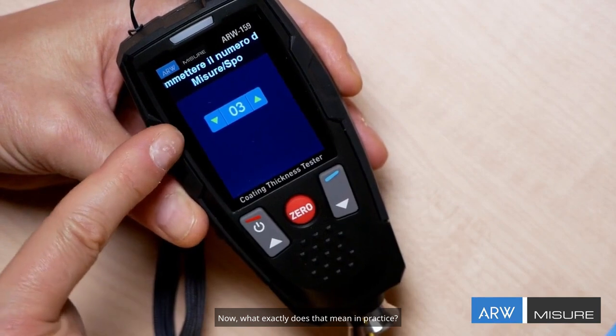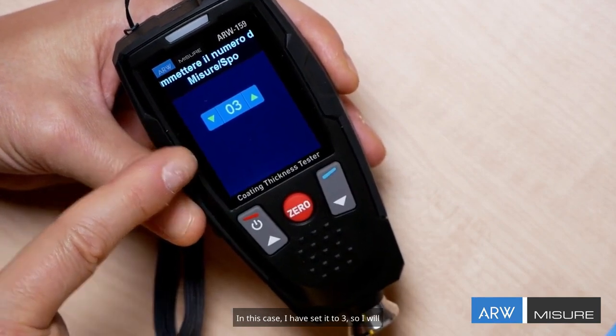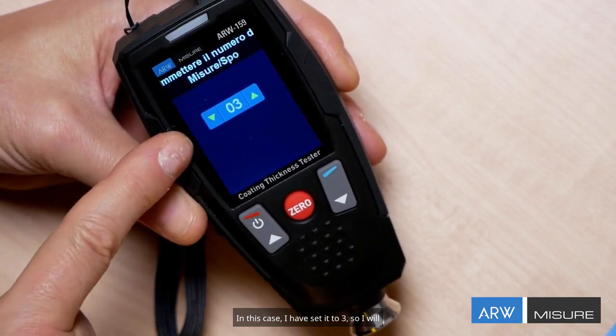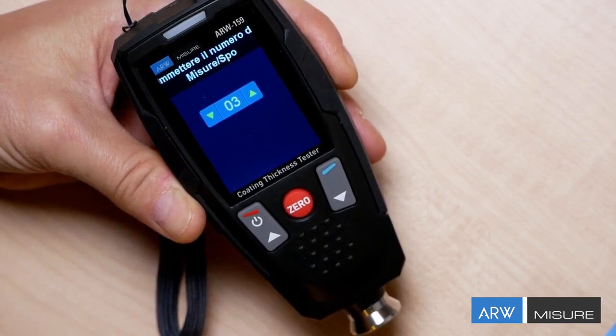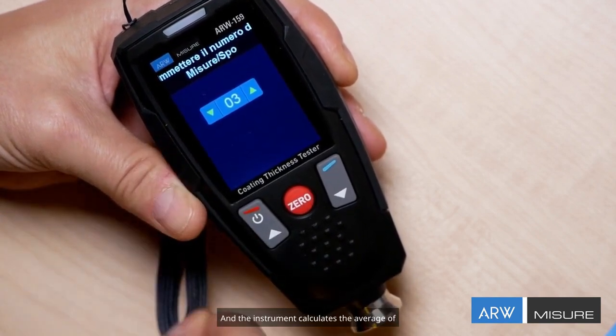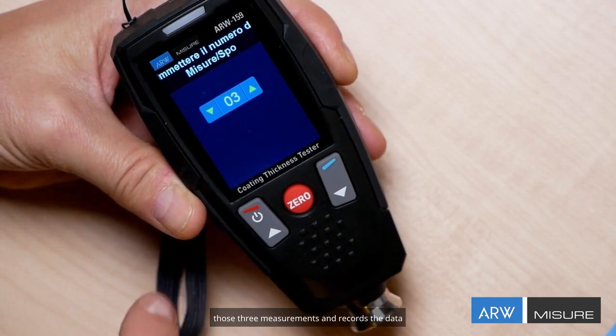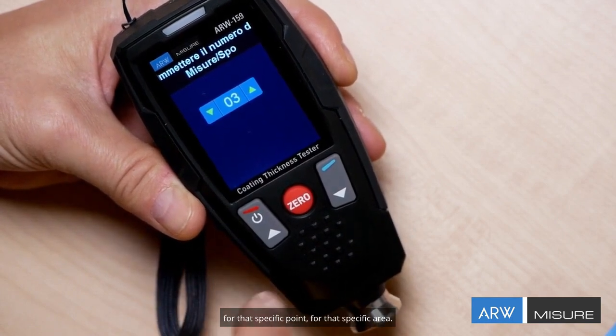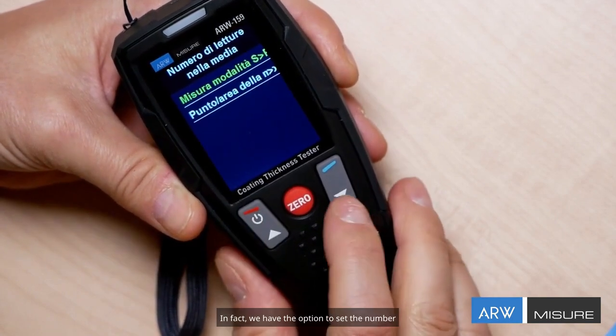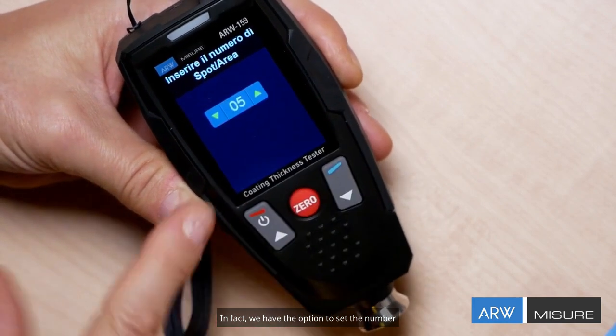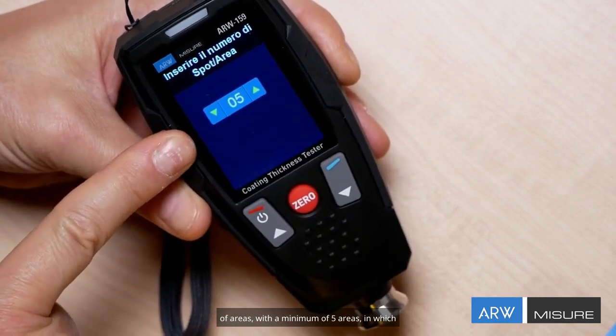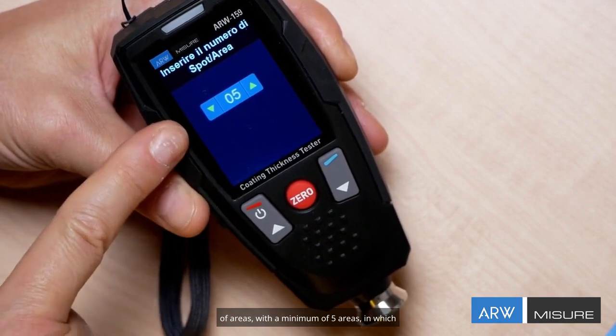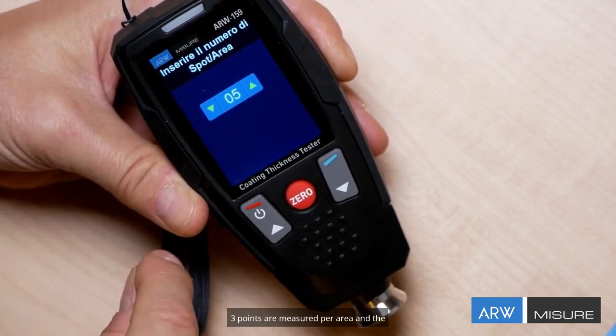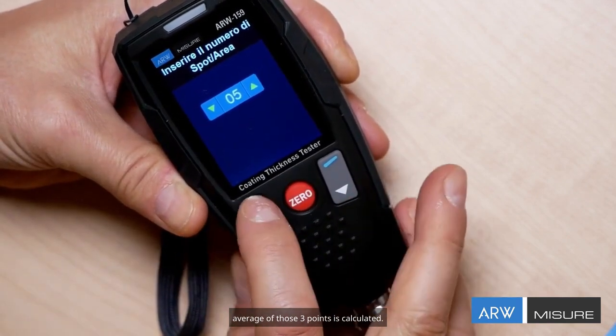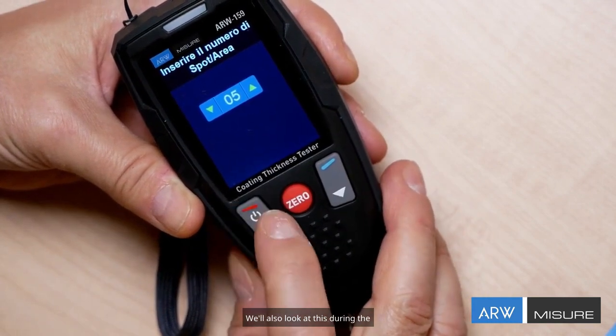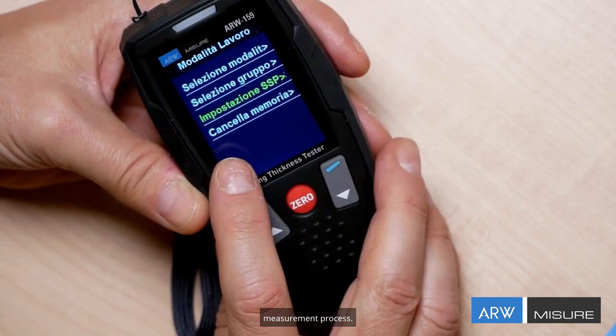Now, what exactly does that mean in practice? In this case, I have set it to 3, so I will take 3 separate measurements. And the instrument calculates the average of those 3 measurements and records the data for that specific point, for that specific area. In fact, we have the option to set the number of areas with a minimum of 5 areas in which 3 points are measured per area, and the average of those 3 points is calculated. We'll also look at this during the measurement process.